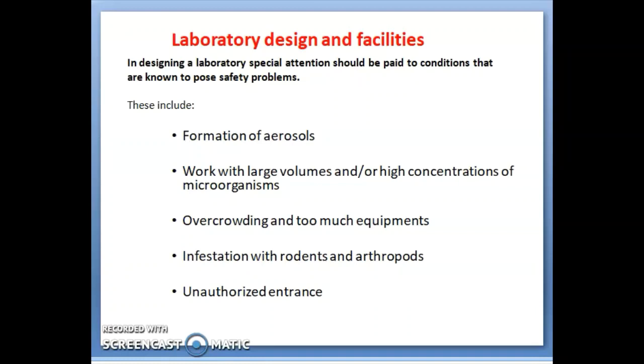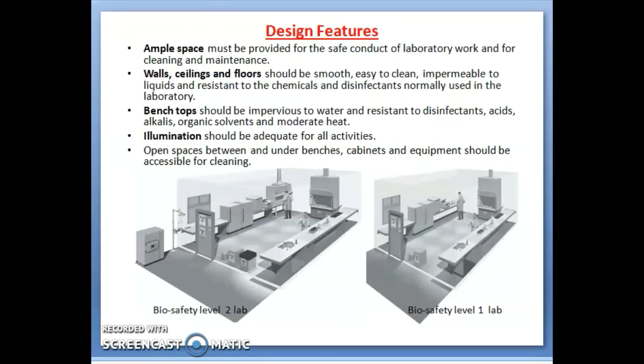In designing a laboratory, special attention should be paid to conditions known to pose safety problems, such as: formation of aerosols; work with large volumes or high concentrations of microorganisms; overcrowding and too much equipment; infestation with rodents and arthropods; and unauthorized entrance. Design features include ample space — enough space must be provided for the safe conduct of laboratory work and for cleaning and maintenance.